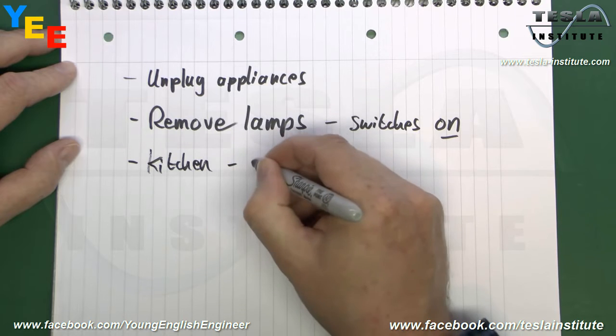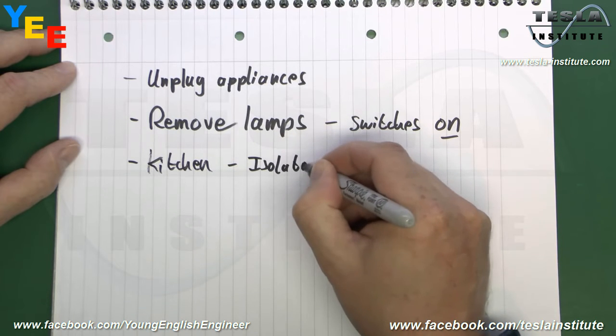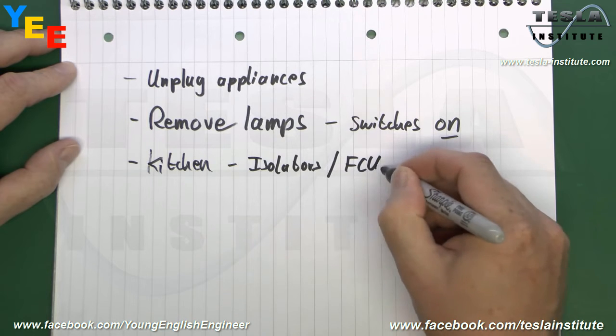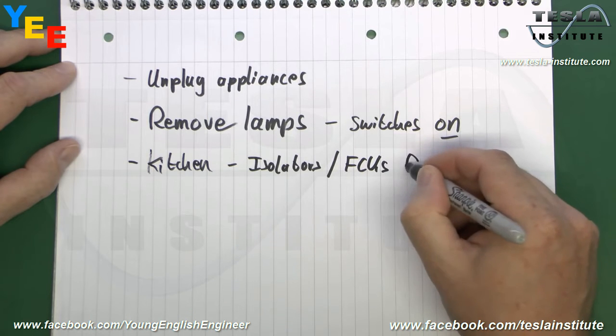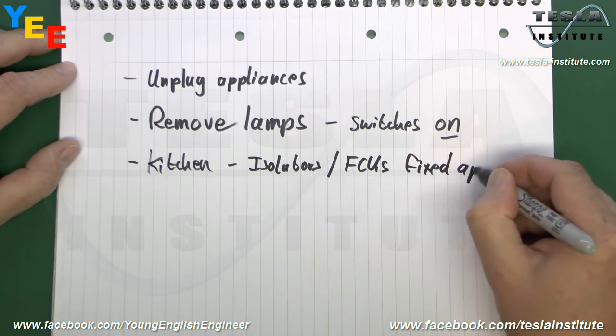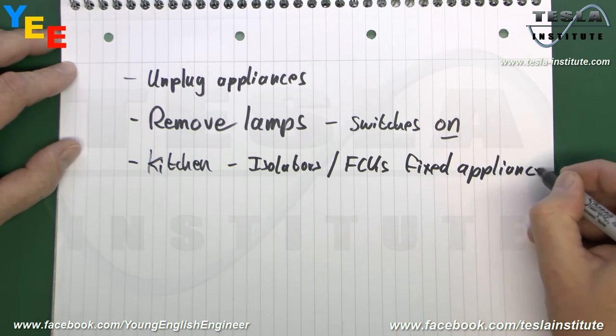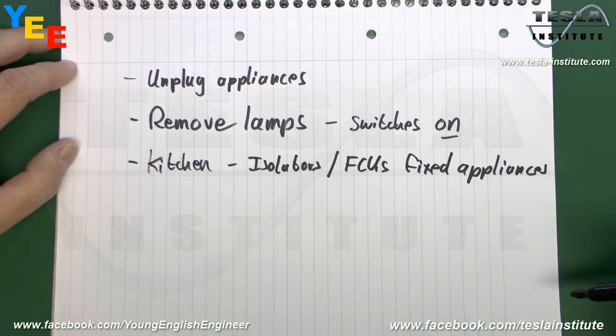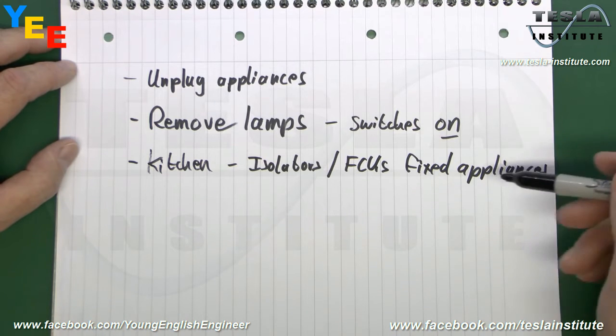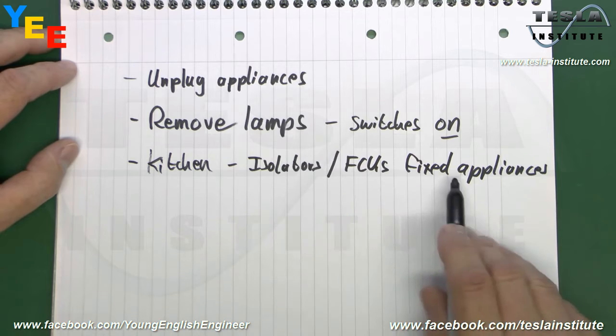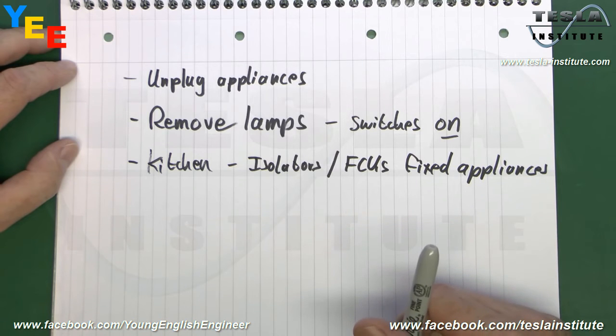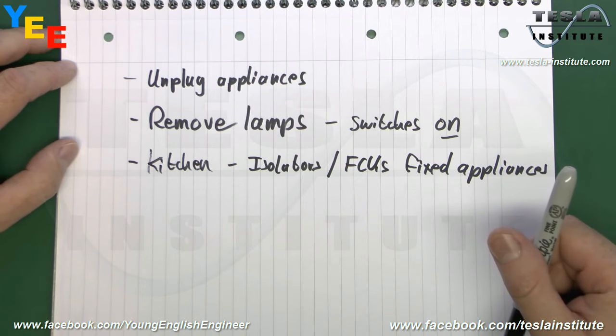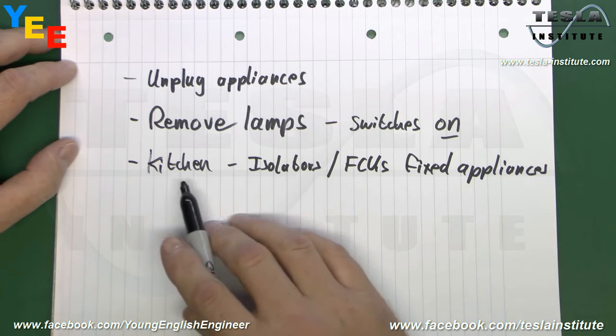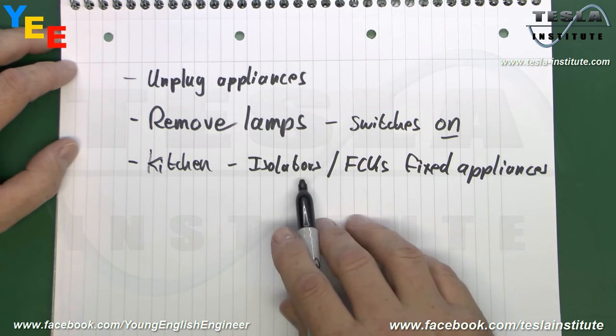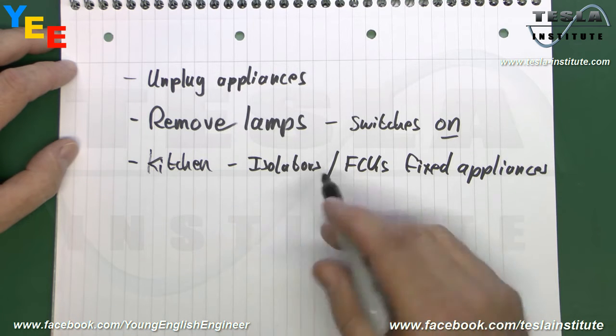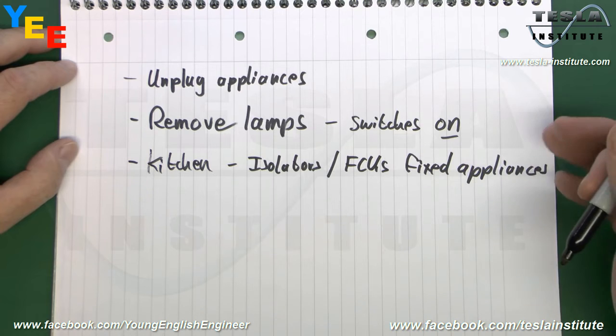So there may be, say, isolators or FCUs or fused connection units for fixed appliances. So things like washing machines and cookers and that kind of thing. And again, you need to either, say, remove the plug in the case of those, or for these, just switch off at the actual isolator or switch or whatever. Again, if it's possible to actually unplug one of these, because you may have a switch and then a socket with the, say, washing machine plugged in, then ideally you would unplug the washing machine. Again, it's all down to what's practical at the time.